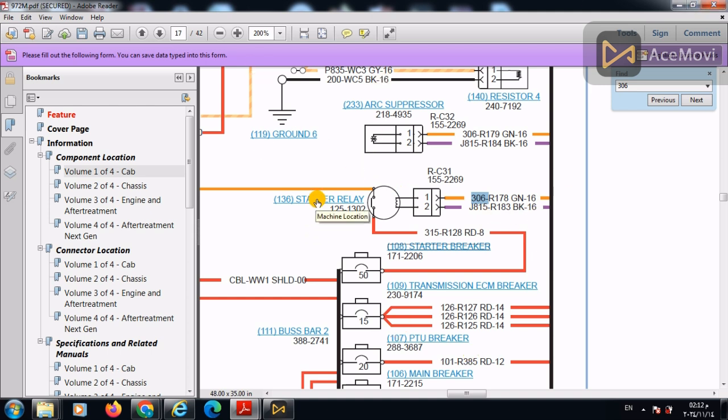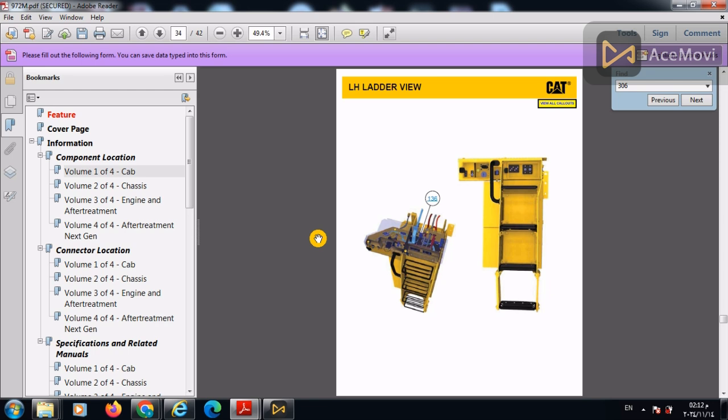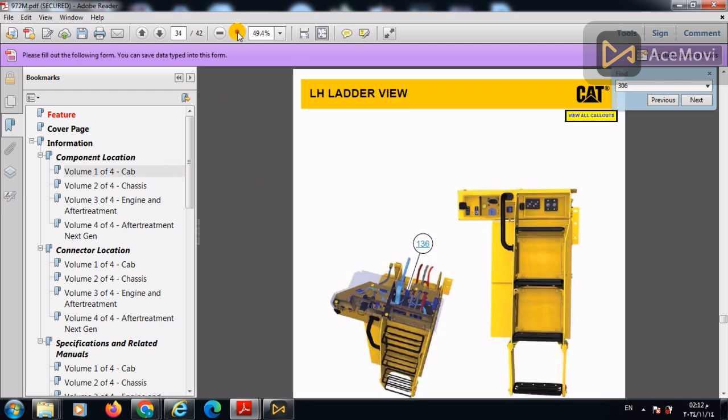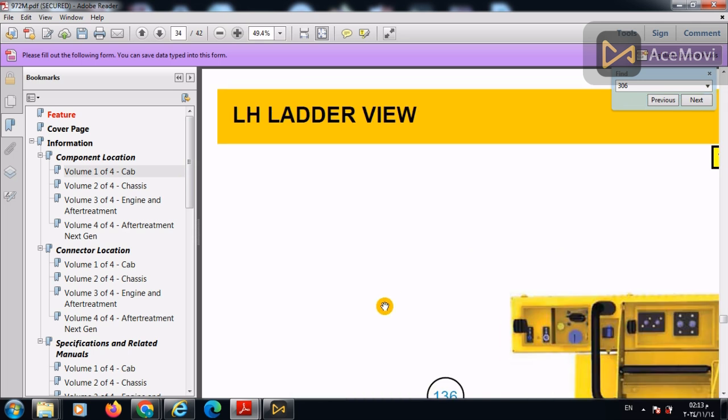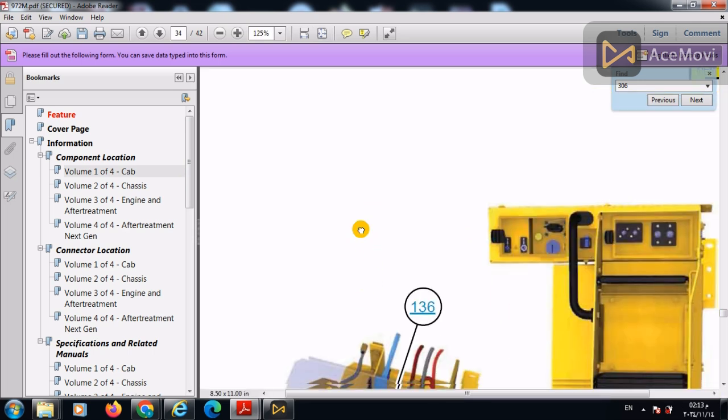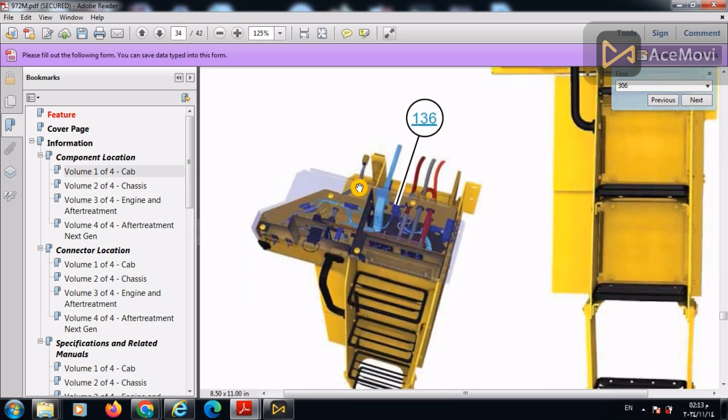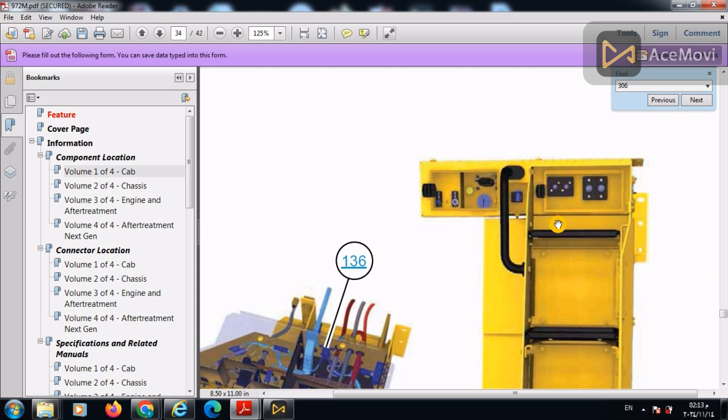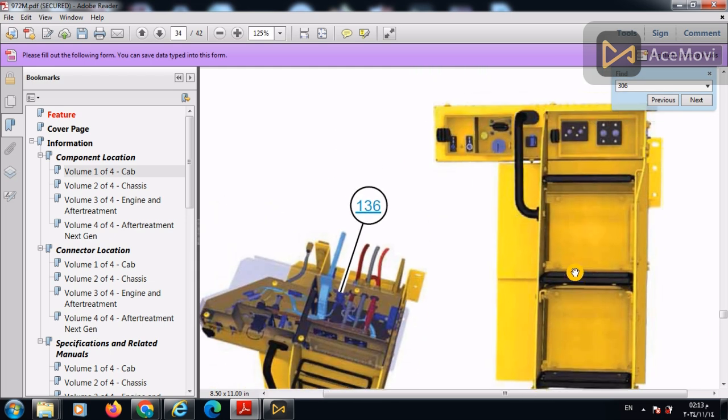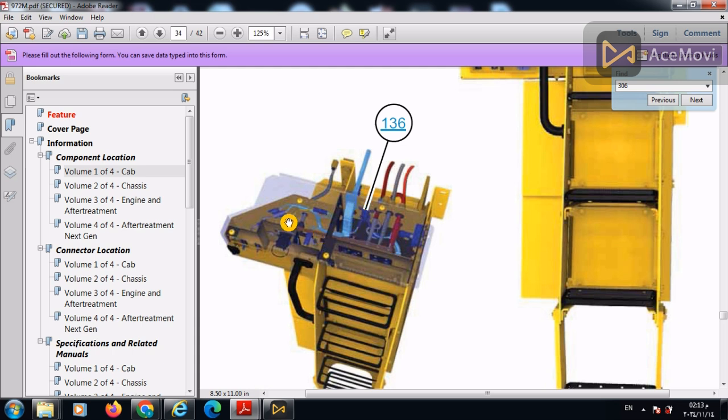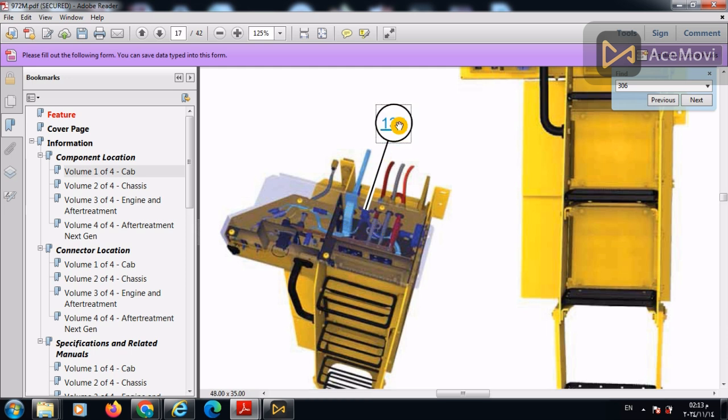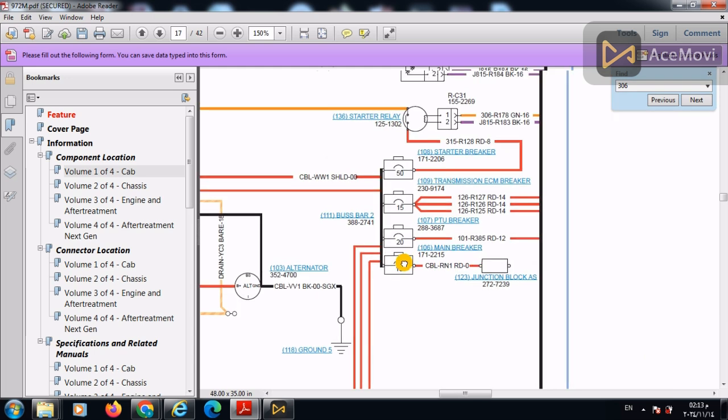In order to know its place, we can press on its hyperlink. We can identify its place by zooming in here. This plate, when you step on that ladder, you can remove this plate, you can find all the relays and the circuit breaker here. So, this is the circuit breaker is mounted with two bolts and there are two wire cables plus a connector that containing our wire 306. By returning back to the schematic.